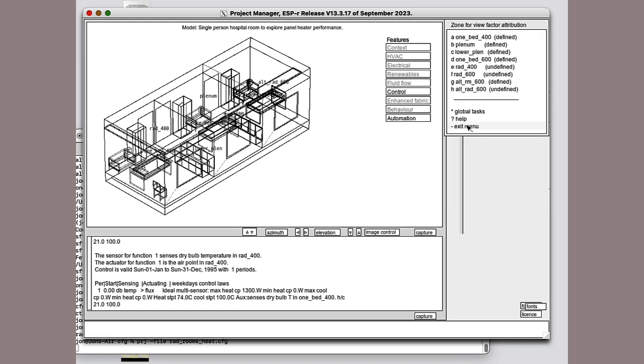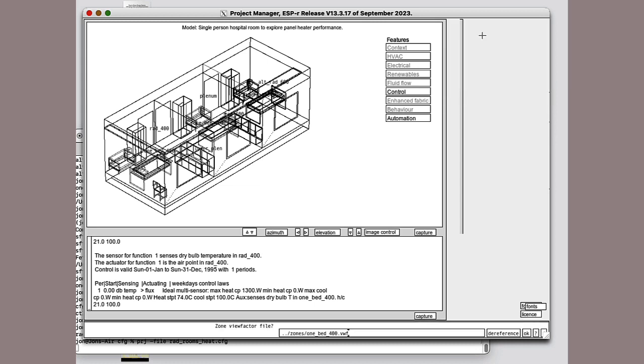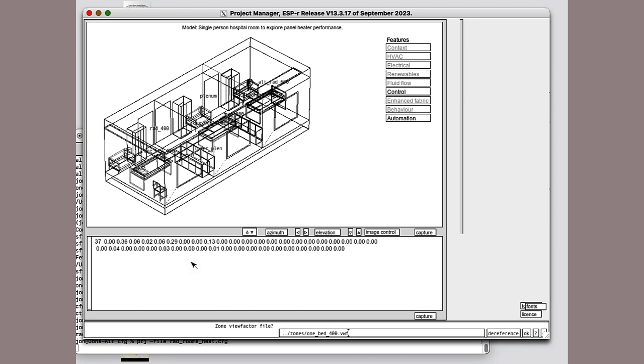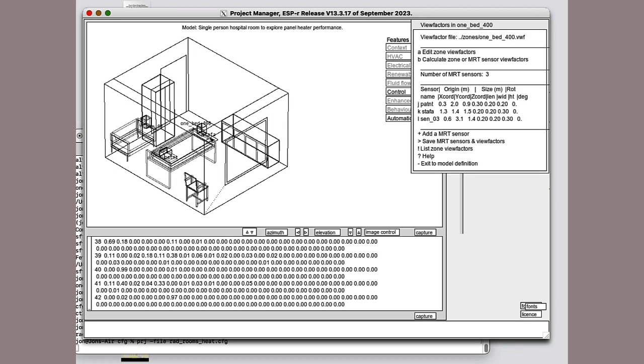In terms of convection coefficients, I have forced a definition within the radiant rooms themselves to make sure that the normal assumptions related to heat transfer coefficients are overridden. One other thing is these sensors that have been defined. They have a position in space and a size. And with that information, we're able to do position-specific thermal comfort analysis.